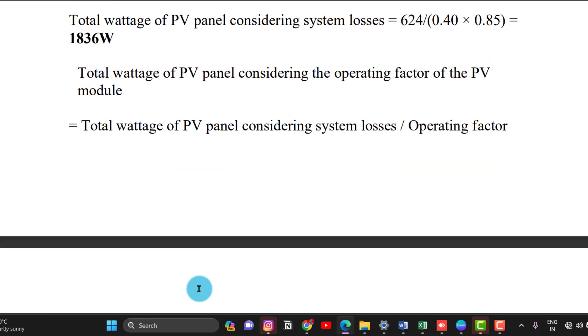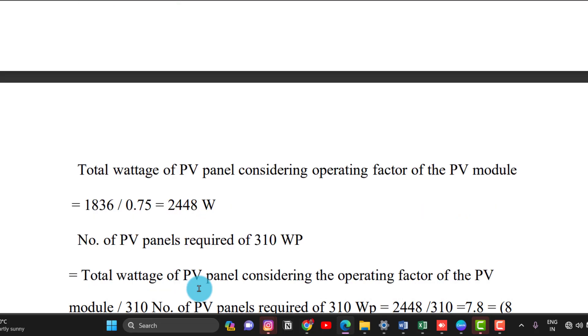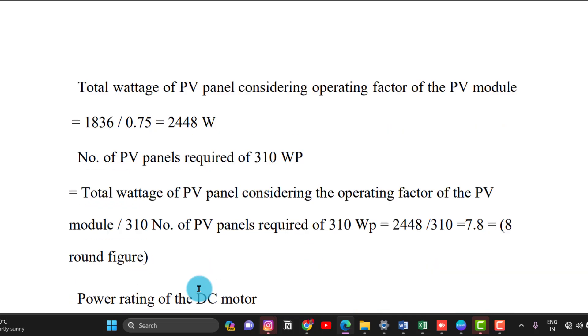Applying the operating factor of 0.75, total required PV wattage equals 1836 ÷ 0.75 ≈ 2448 watts. This is the power requirement to pump 50,000 litres per day. Number of panels required equals 2448 ÷ 310 Watt peak ≈ 8 panels. So 8 solar panels of 310 Watt peak are needed.